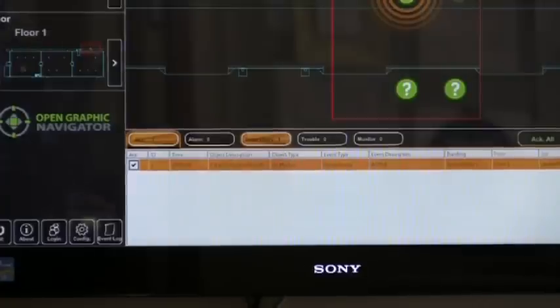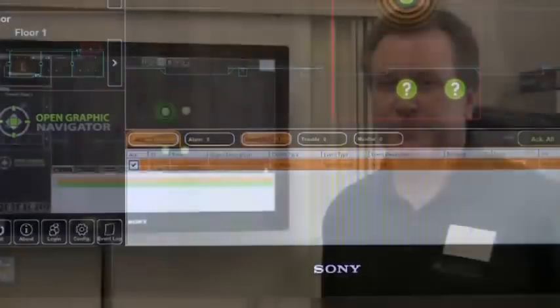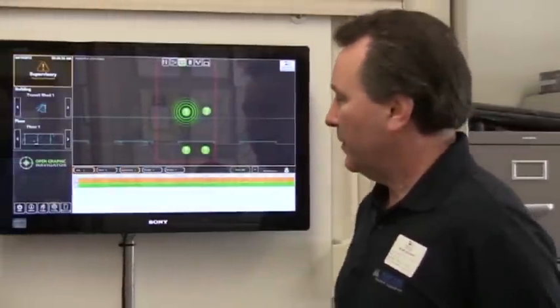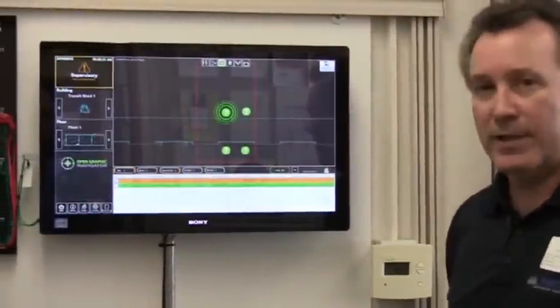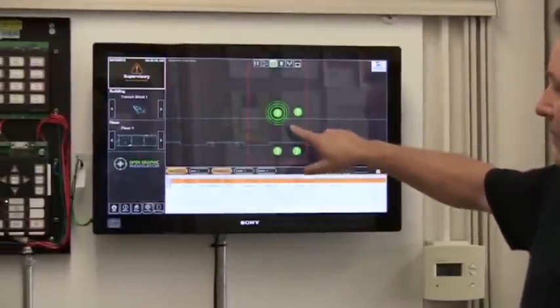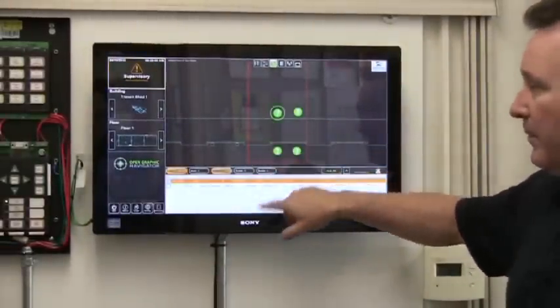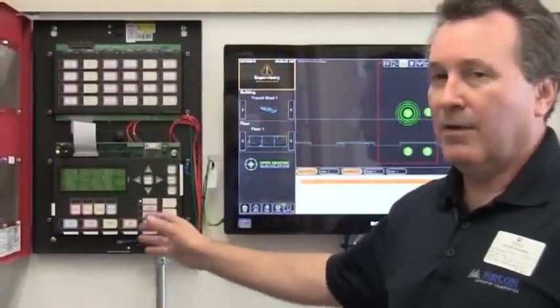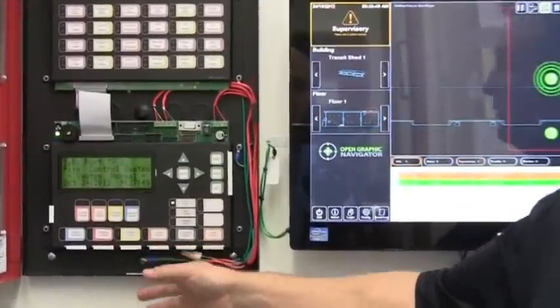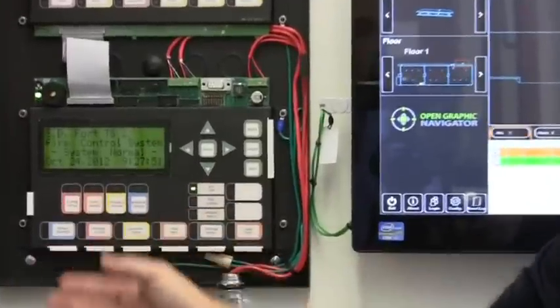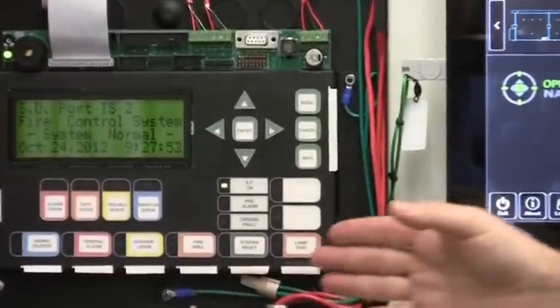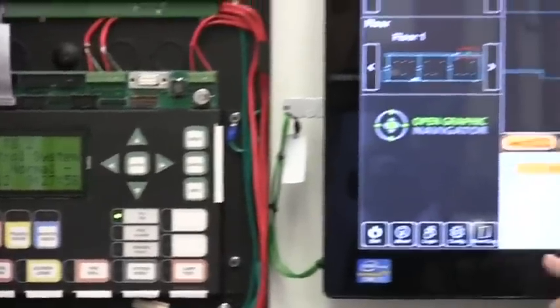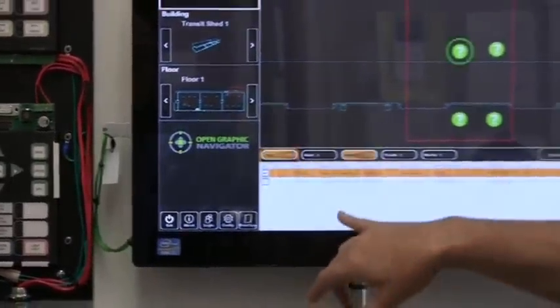Joe goes over and restores that event from the previous supervisory condition. When the event has been restored, it turns green, meaning it's good to go. On the fire alarm panel LCD, supervisory and trouble events, once they've restored, clear themselves — there's no user intervention required. All that's left now is on the graphic annunciator are the events that have been unacknowledged.